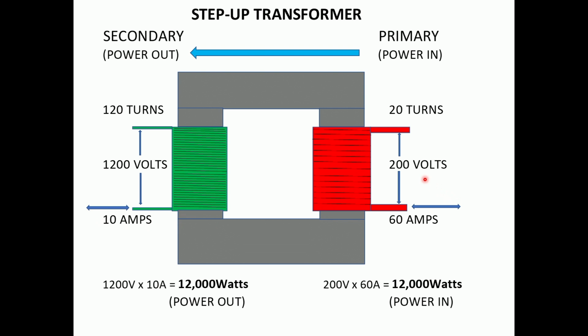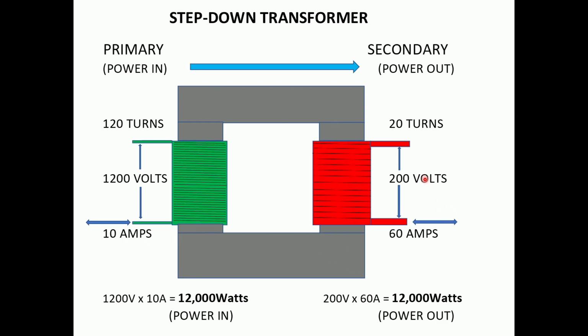Let's take a look at a step-down transformer. Looks the same, doesn't it? Well, it is - it's the same drawing, except we're putting the power in on this side and taking it out on this side. So the ratios are the same, 120 turns to 20, that's 6-to-1. If I apply 1200 volts across here, I will only get 200 here. However, if I draw 60 amps through this coil, I only have to provide 10 on this coil. Again, 12,000 watts in, 12,000 watts out.